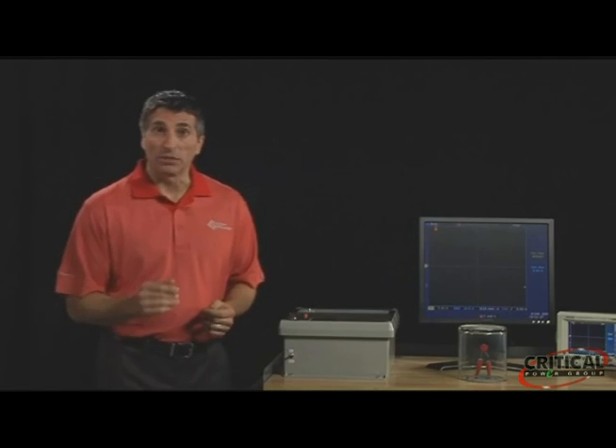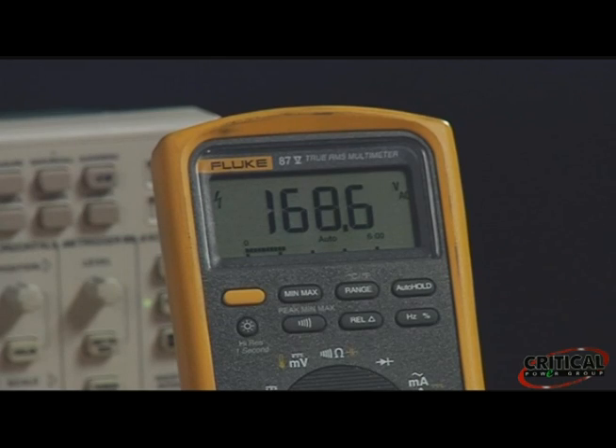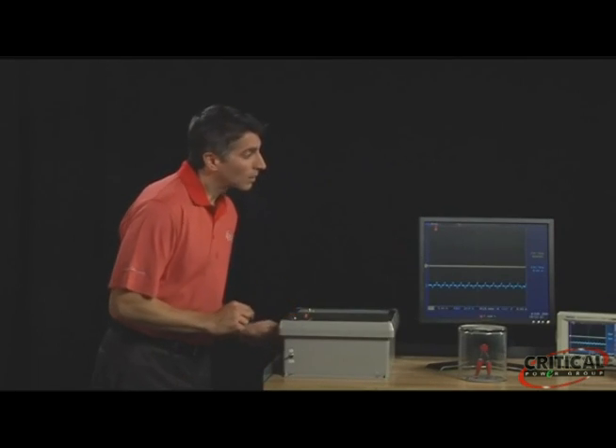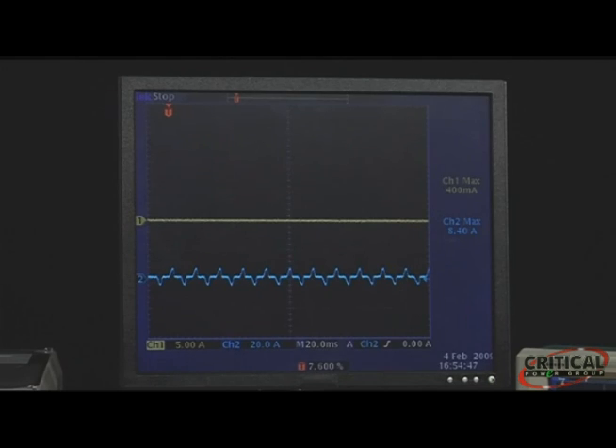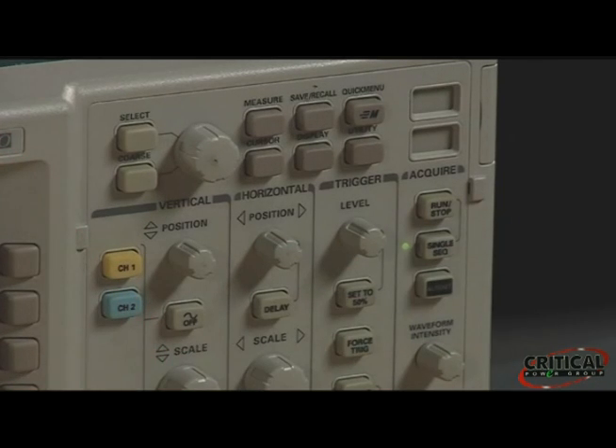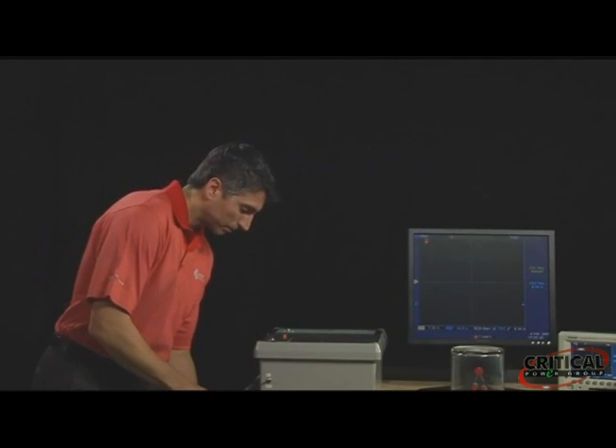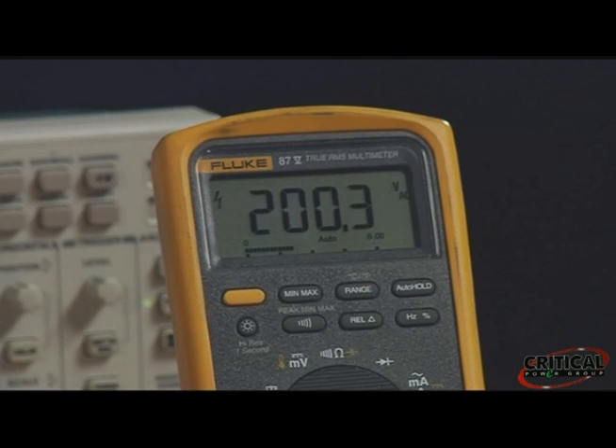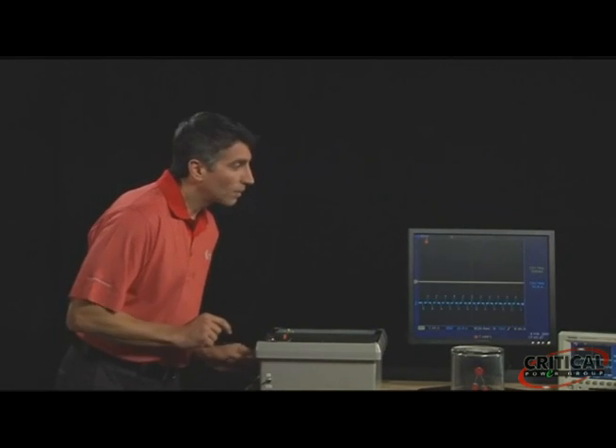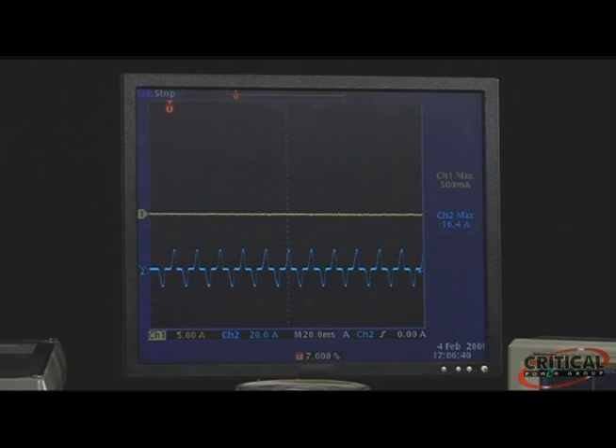Now we'll increase it to 170 volts. And as we can see on the monitor, there was no current flow through the MOV. It did not clamp and provided no protection at this voltage. However, the selenium cell has begun to clamp. It is now providing protection to both the MOV as well as the downstream equipment. Now I'll just reset the scope. We'll now increase the voltage to 200 volts. At 200 volts, we can see that the selenium cell is still providing protection with 16.4 amps flowing through it.